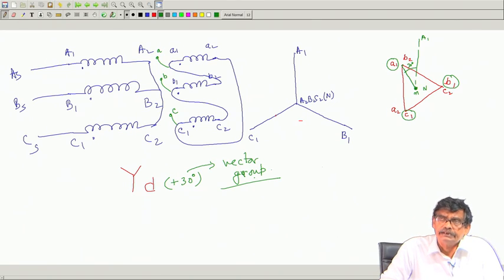Given three single phase transformers, without doing polarity test, do not go to connect the 3 phase connections, either star star, delta star. It will then be left to chance. Particularly with delta connections, you may face a disastrous condition, short circuiting the supply.